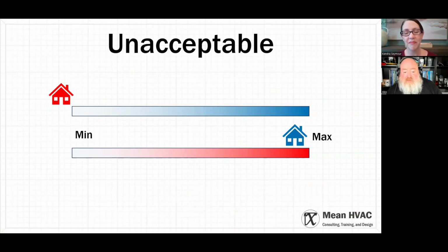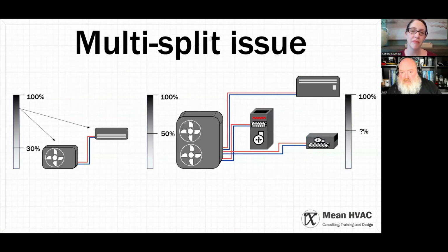The budget for these mini split systems can be kind of tight, so they'll sometimes push you into one outdoor unit with multiple indoor units. The problem is these don't ramp down the same way. The outdoor unit can run lower if it needs to than the individual indoor units can, and what they don't always tell the contractor is that the individual units can only ramp down so low.